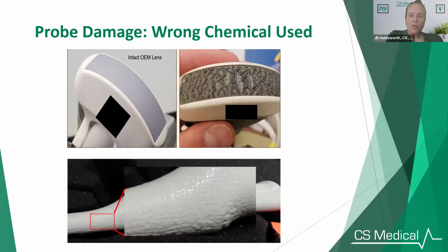So I want to show you some pictures of what can happen when you don't do these processes correctly. Sometimes in facilities, we use the wrong chemical. Some people aren't sure what to do their manual cleaning with, like what to put in the water. So you've automated your high-level disinfectant, but you still have to clean. Even when you are manually cleaning, sometimes we're not using an approved product. Approval of chemicals is so important because you can damage your probes so quickly. So these are some probes where the wrong chemical was used somewhere along the line of the process. And I know some of you are probably cringing, thinking, wow, they just ruined that very expensive probe. Now they've got to replace it. These are not recoverable in some cases. So maybe that top one, maybe we could replace that. But sometimes you can't recover these and you just have to replace the whole thing.